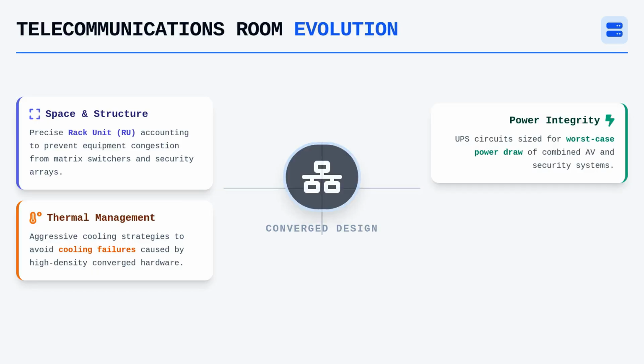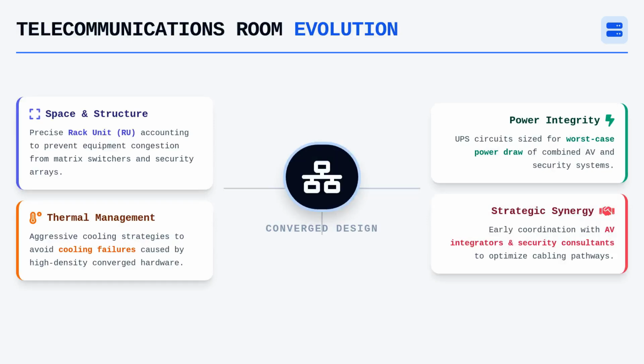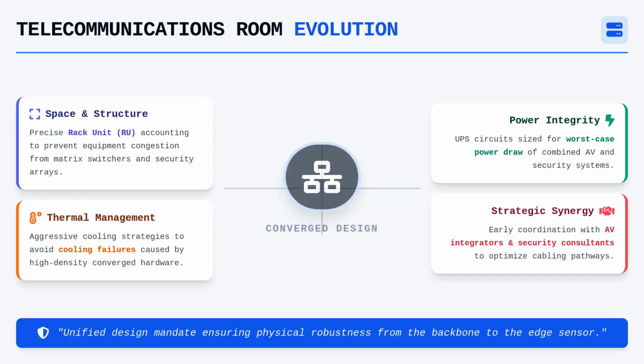Dedicated, uninterruptible power supply circuits must be sized not just for nominal loads, but for the worst-case power draw of all security and AV hardware residing within that room. We must coordinate extensively with external security consultants and AV integrators early in the design phase to avoid redundant cabling or, worse, undersized pathways. When we unify these systems under a single design mandate, we ensure physical robustness that spans from the backbone to the most edge-based security sensor.